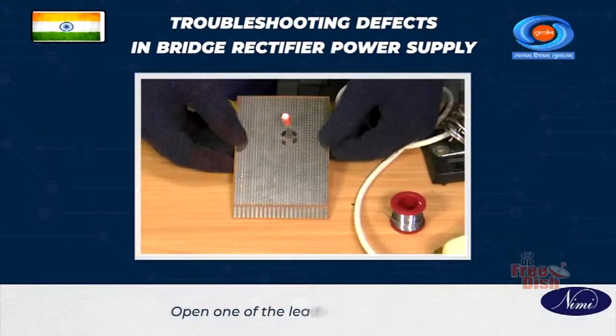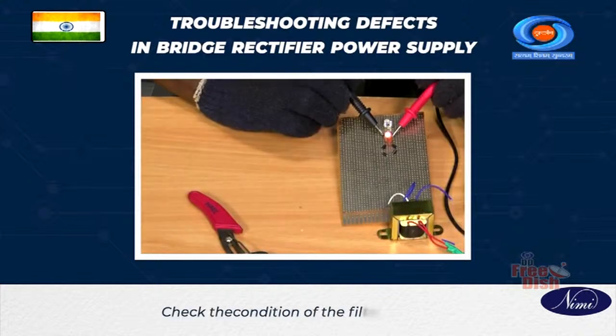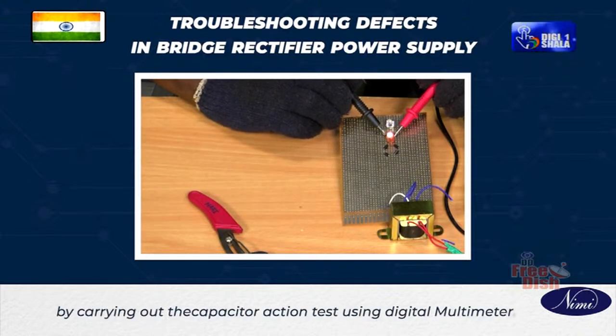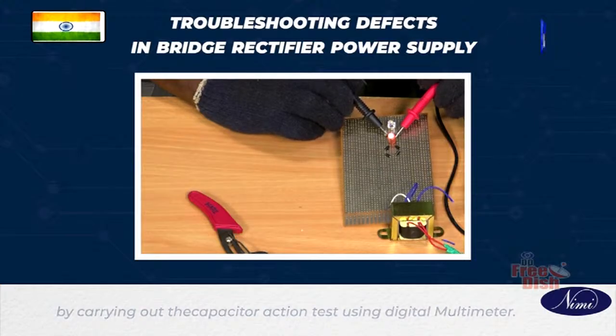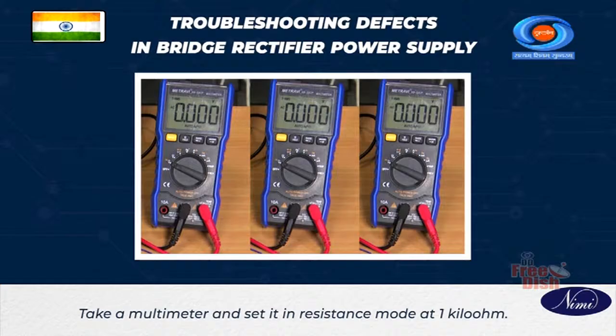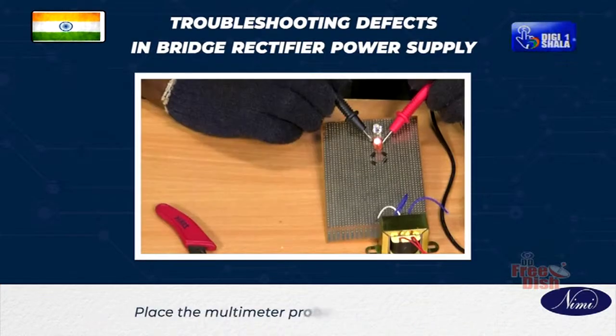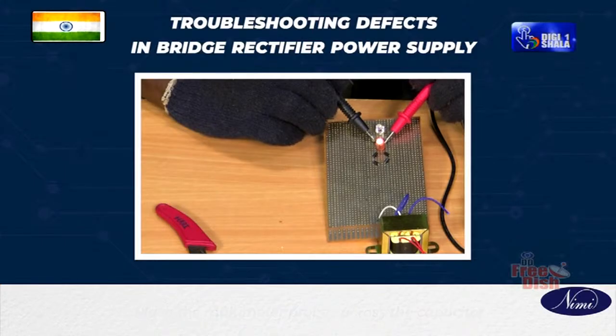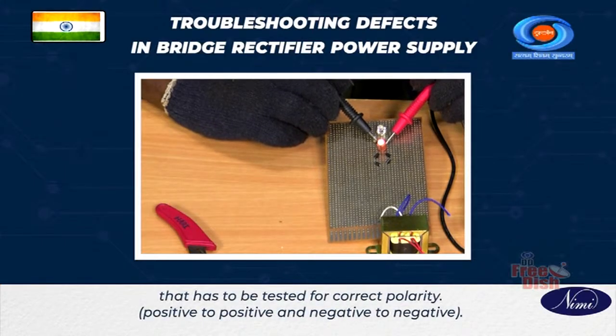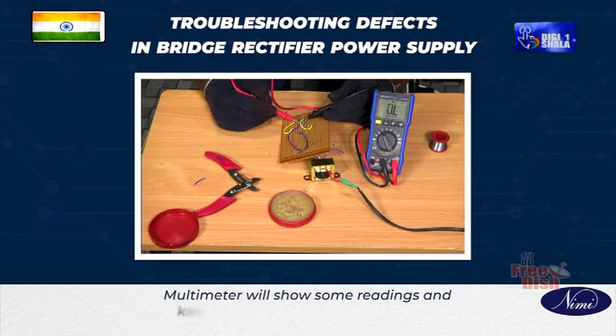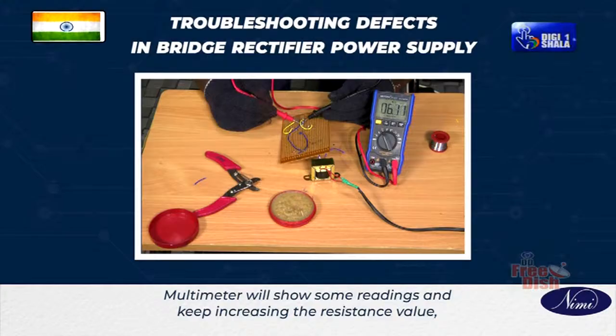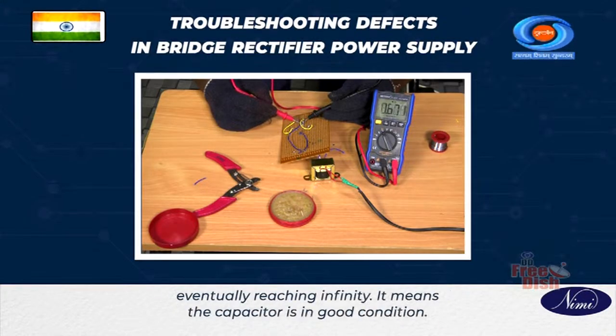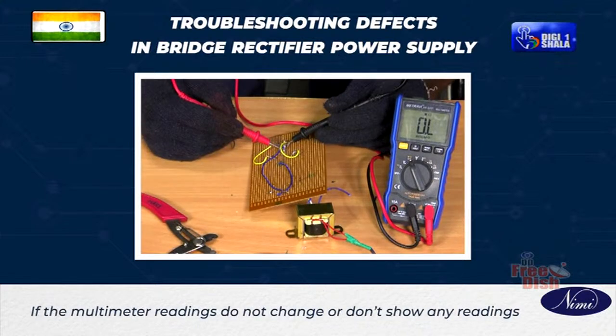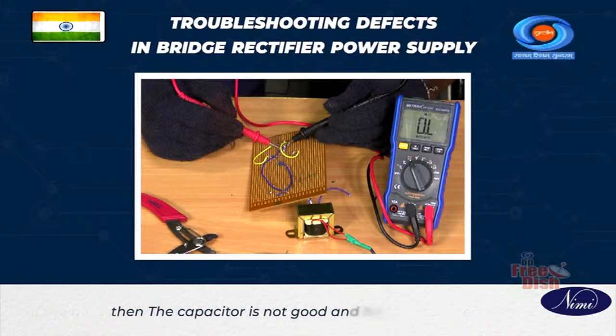Step 8. Open one of the leads of the capacitor. Check the condition of the filter capacitor by carrying out the capacitor action test using a digital multimeter: 1. Take a multimeter and set it in resistance mode, 1 kilo-ohm. 2. Place the multimeter probes across the capacitor to be tested for correct polarity, positive to positive and negative to negative. 3. The multimeter will show some readings and keep increasing the resistance value, eventually reaching infinity, meaning the capacitor is in good condition. 4. If the multimeter readings do not change or don't show any readings, the capacitor is not good and has to be replaced.